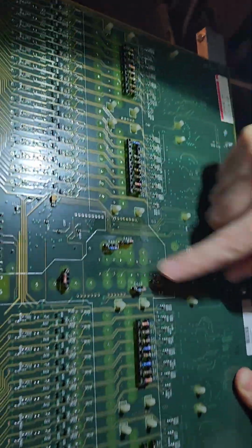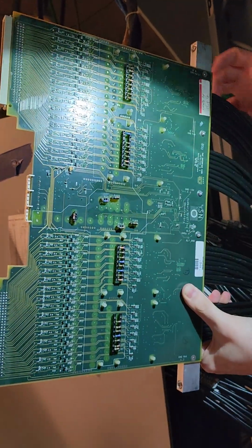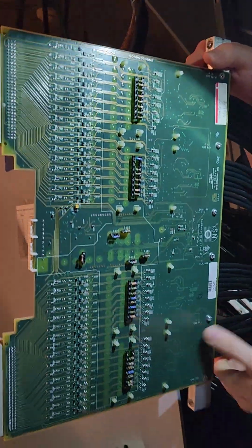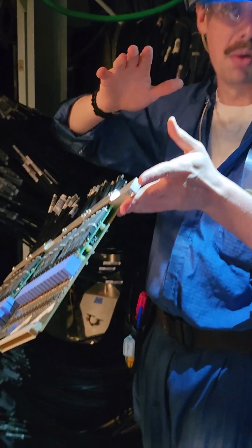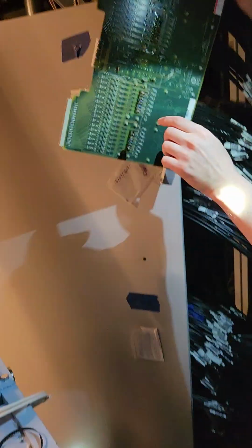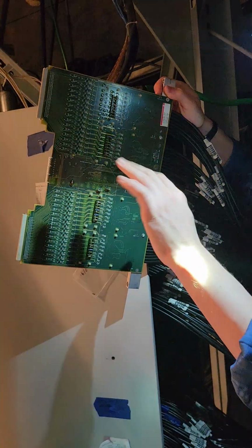Once it's past this resistor, it branches out again into a parallel group of 8 to then feed each one of the PMTs. Every PMT was tested way back in the day to figure out what its nominal voltage is. Every PMT is its own unique device, right? They'll have more or less gain depending on what voltage you send, so you can tweak it a little bit. Each one of these resistor values is set to tune it to where it's happiest within a certain region.